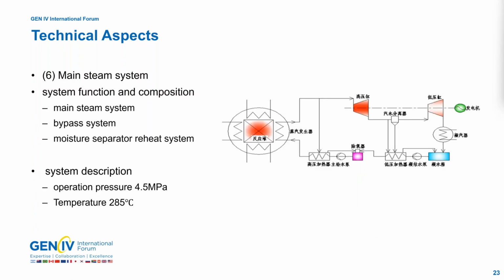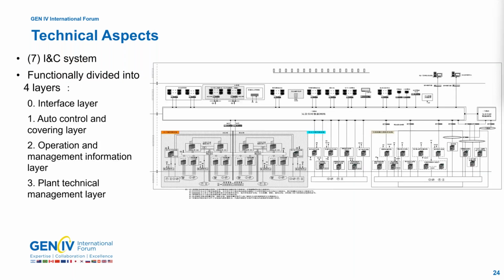The main steam system is composed of main steam system, bypass system, moisture separator, reheat system. And the system description: operation pressure is 4.5 megapascal, temperature is 285. Next, please. Next, please. The I&C system, the function of I&C system divided into 4 layers: the interface layer, auto control and processing layer, operation and management information layer, the plant technical management layer. Next, please.